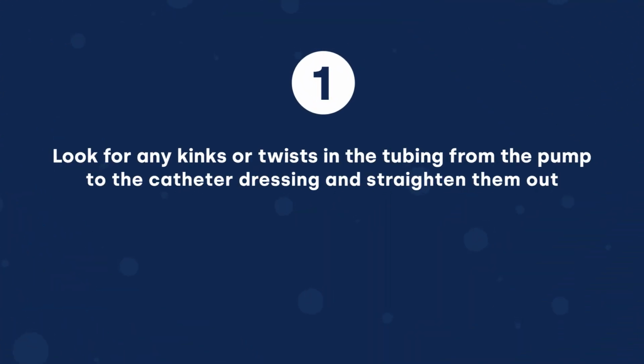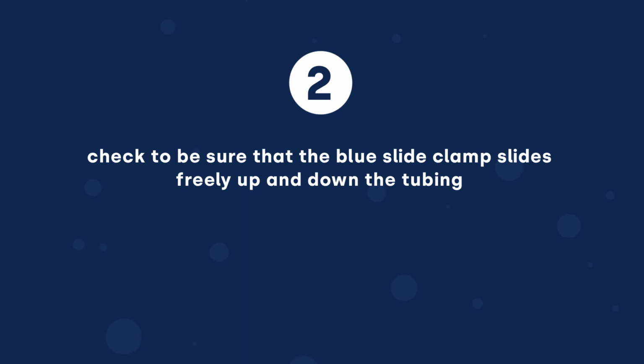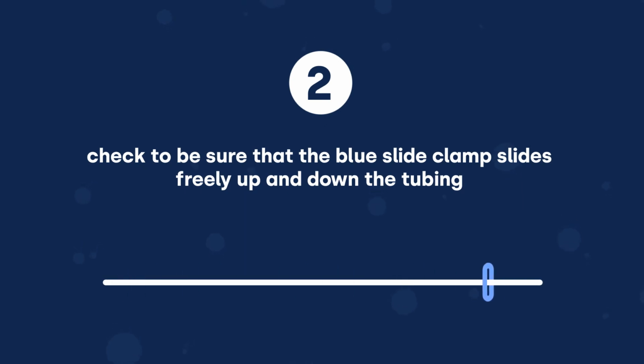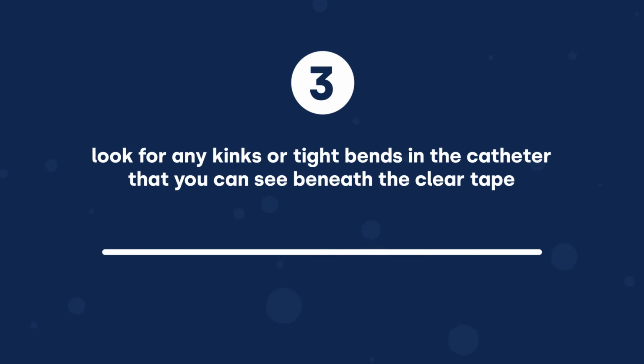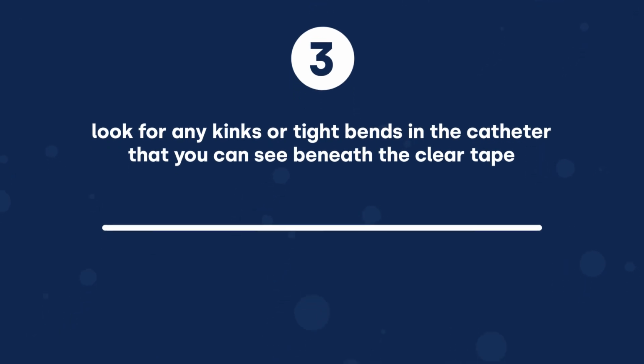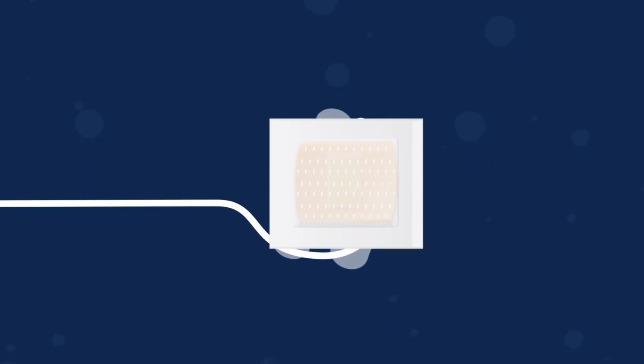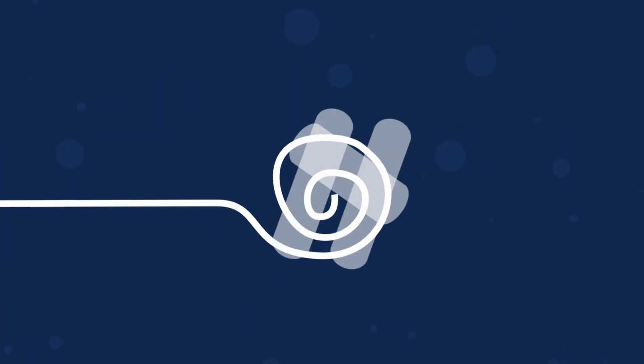First, look for any kinks or twists in the tubing from the pump to the catheter dressing and straighten them out. Second, check to be sure that the blue slide clamp slides freely up and down the tubing. Third, look for any kinks or tight bends in the catheter that you can see beneath the clear tape. If a kink is visible, you can attempt to straighten it while being careful not to remove any of the tape or disturbing the dressing.